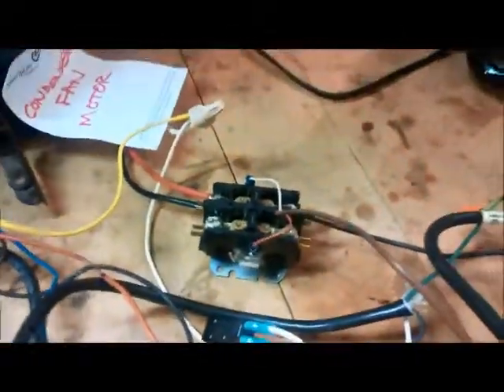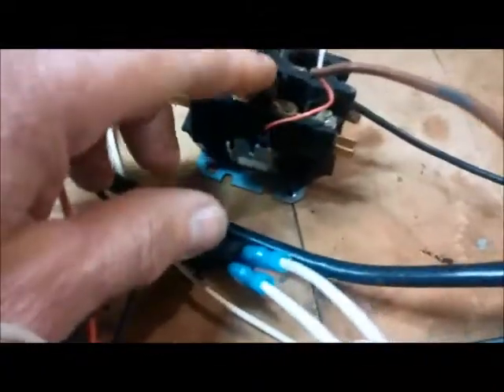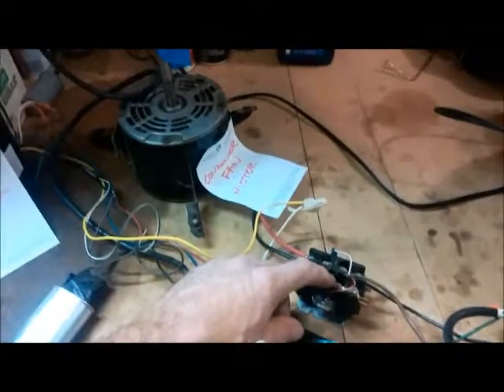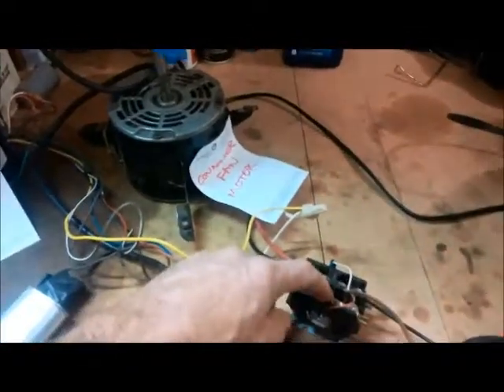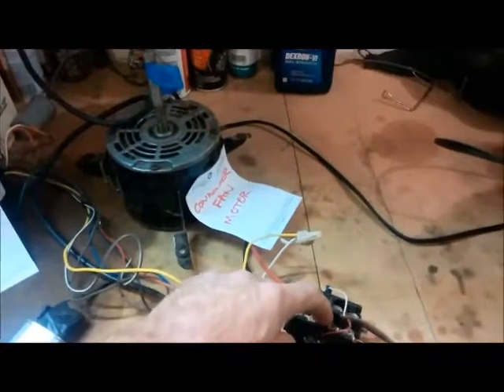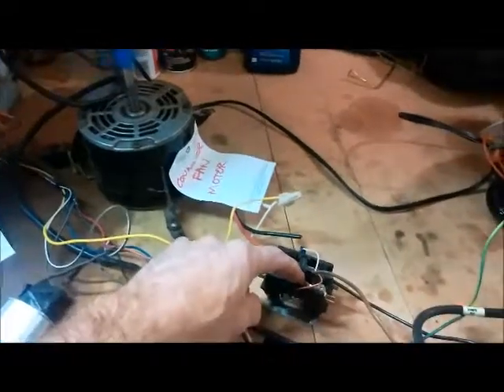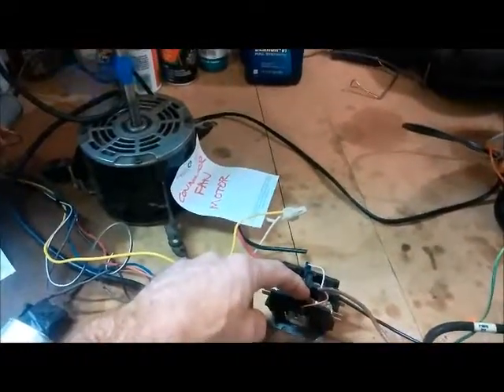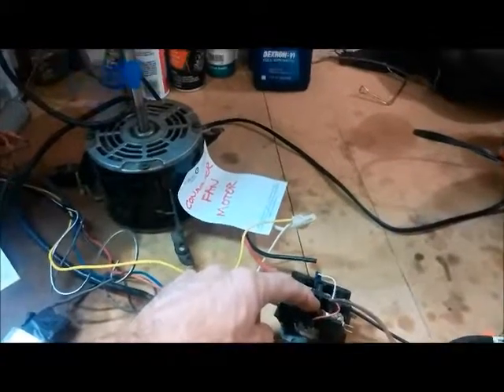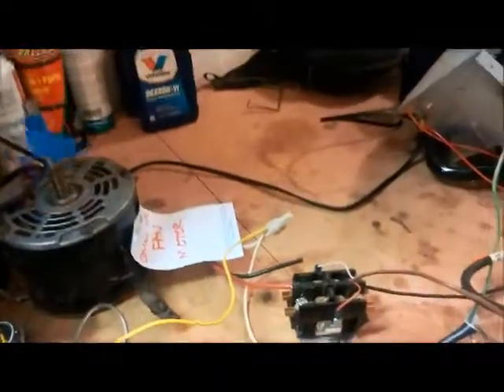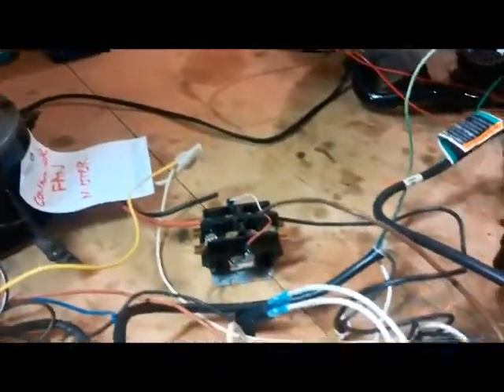So you could do that to see if you have power out there. If you just want to see if you have power, you can just push in the contactor. Of course, don't touch anything metal there. You're going to get shocked. And when you push that in, your compressor should be running as well as the condenser fan motor. So on a call for cool, we should have 24 volts across that coil.